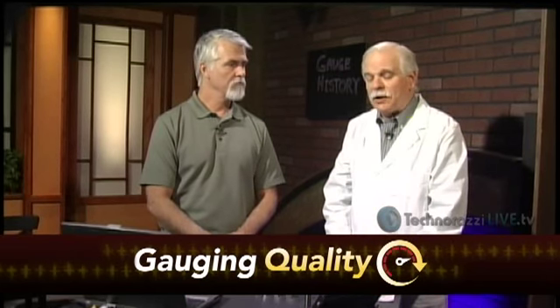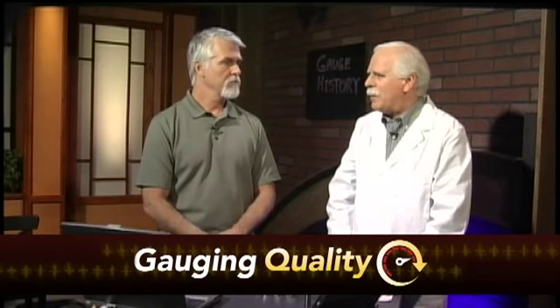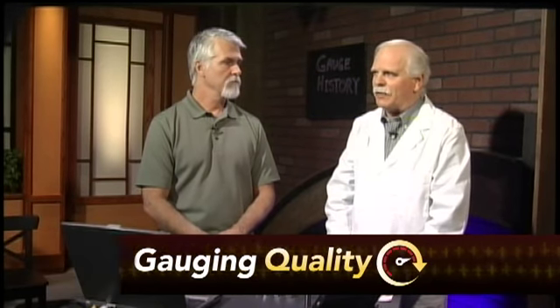If you do extend the interval, which is asked quite often, if there is a problem, the question is what happens? Well, the last time it was calibrated is the only time you know it was in tolerance. It's more of a gamble. How much can you afford? How much product can you check with it and afford to be out? If you're only checking things once every 6 months, it's not nearly the same gamble as if you're running it three shifts a day.